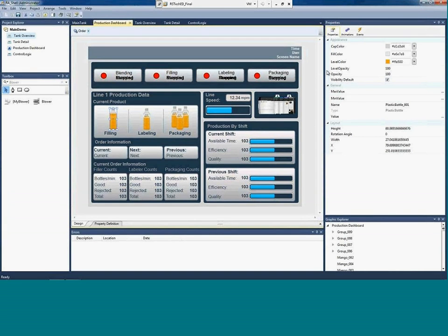That's through an events and commands infrastructure that is very similar to what you might be familiar with in SE, where based on an event trigger I want a command to be run. And then also the ability to build state tables, so that based on the incoming data from a tag or an expression, I can choose to set a whole host of different properties. So all of that behavior, all those different methods, can be wrapped up and encapsulated in an add-on graphic, which gives it the same kind of power that an add-on instruction has too.